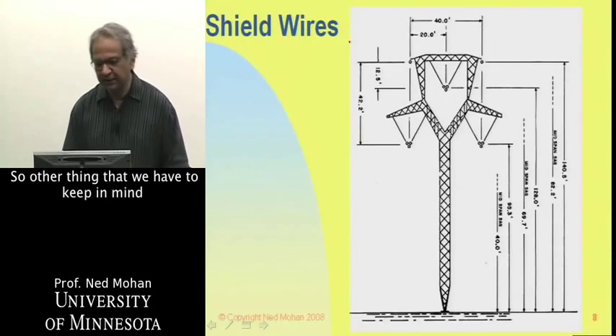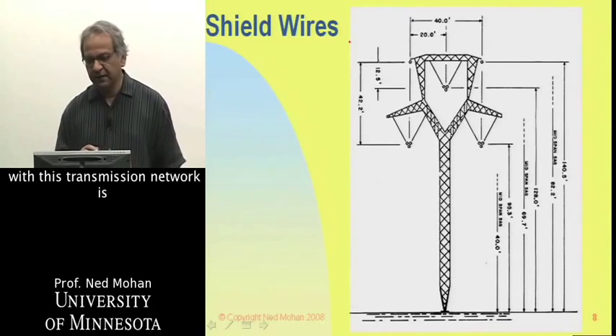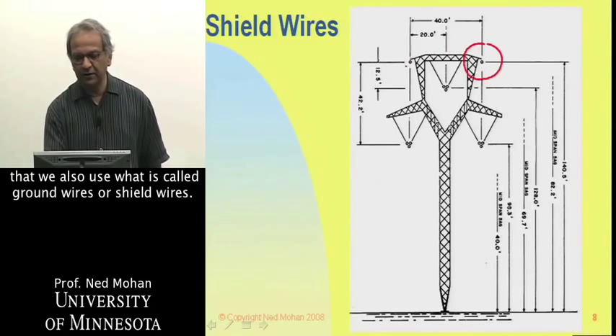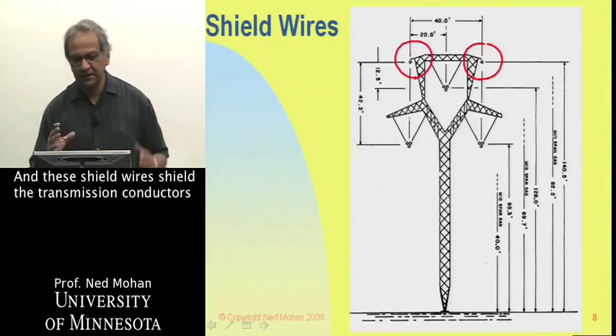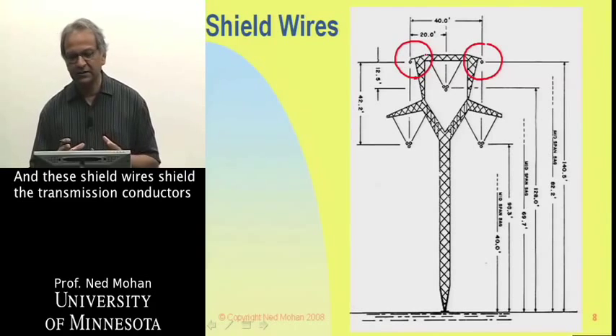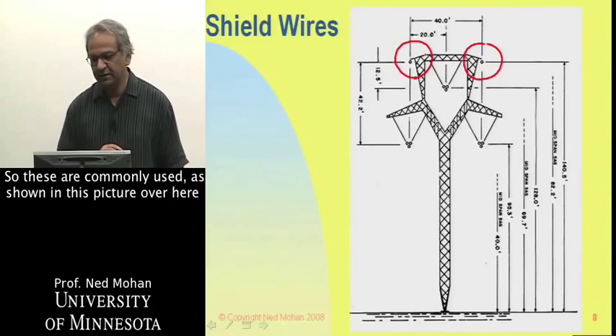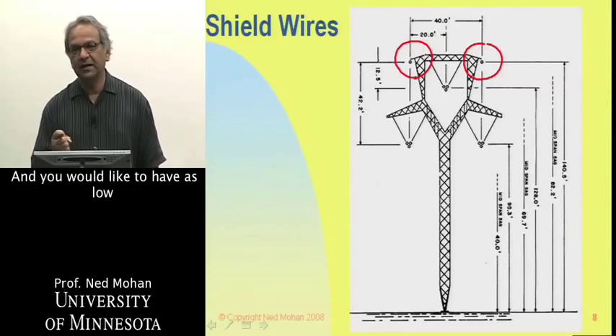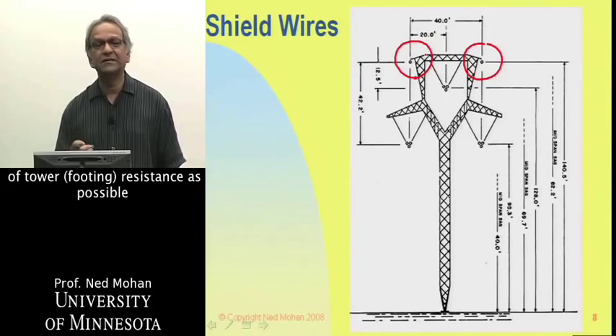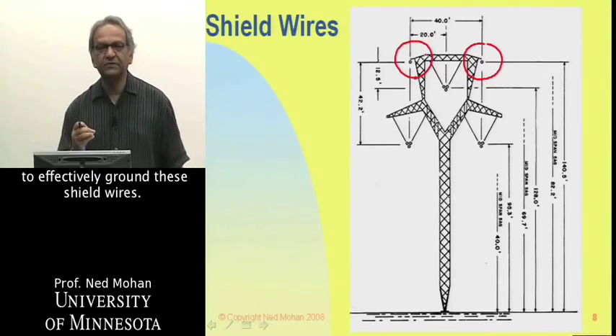Another important feature of transmission networks is the use of ground wires, also called shield wires. These shield wires protect the transmission conductors from lightning strikes, and they are commonly used as shown in these pictures. Every so many towers, these shield wires are grounded, and you want as low a tower footing resistance as possible to effectively ground them.